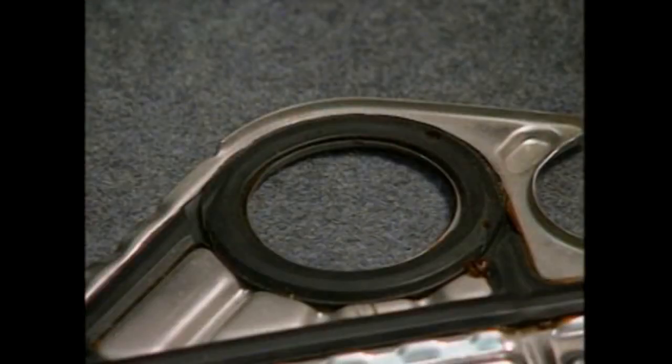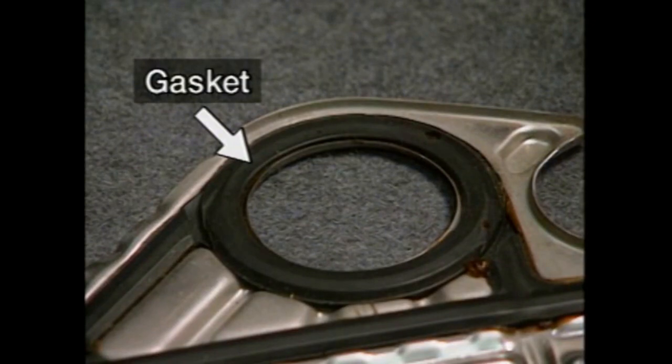Between each two plates is a gasket which separates the plates and creates a channel between them. The gaskets also seal the plates together so that the process fluids won't leak out of the heat exchanger. The gaskets also seal around the portholes so that the two fluids won't mix together and contaminate each other.